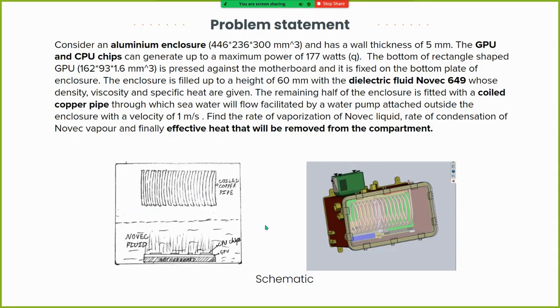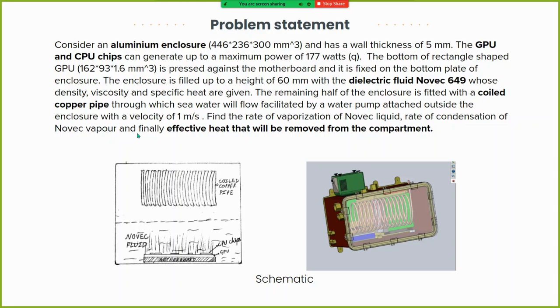The problem statement: the aluminum enclosure dimensions and wall thickness are given. The CPU and GPU chips generate a maximum power of 177 watts. Novec dielectric fluid is filled to a height of 60 mm, with its properties given. The remaining enclosure space contains the coiled copper pipe through which the coolant flows, facilitating condensation of Novec vapor. We need to find the rate of vaporization of Novec liquid, the rate of condensation of Novec vapor, and the effective heat removed from the compartment.